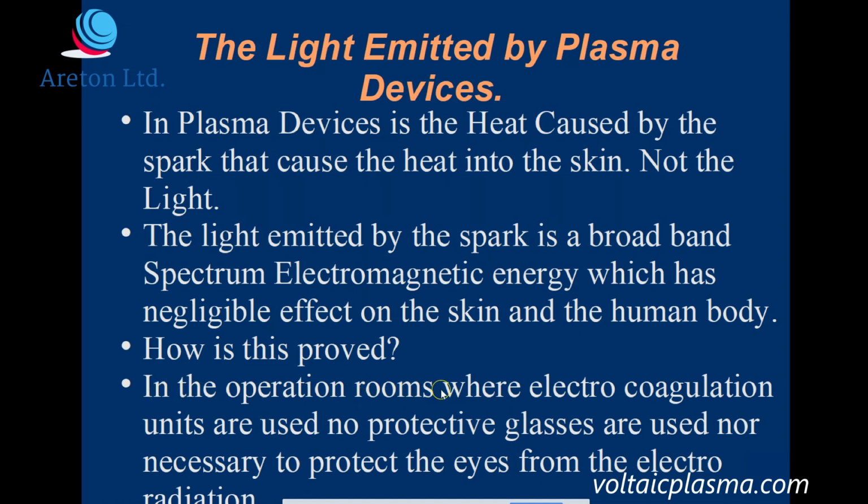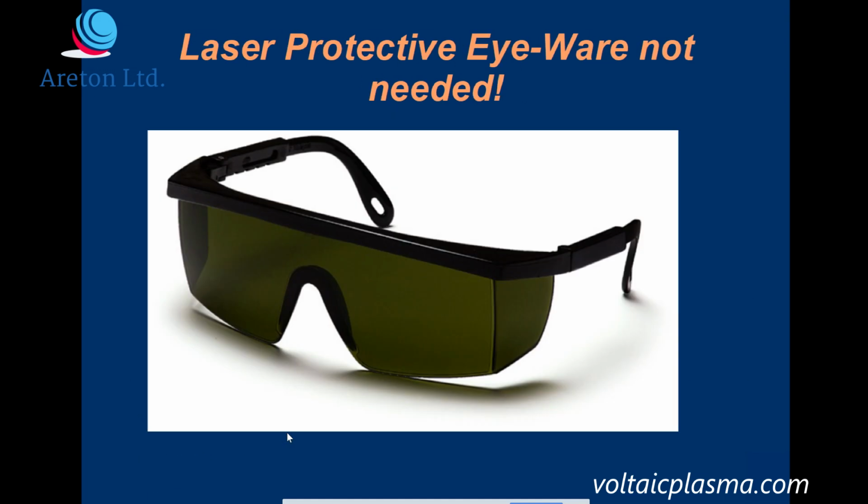In the operation rooms, one of the proofs is that, as I said before, this has been used in the operating theatre for several years, since the 40s, 50s. And no one has ever used any eyewear protection in using electrocoagulation units. It's just a fact. So laser protective eyewear is not needed, nor is it for IPL.